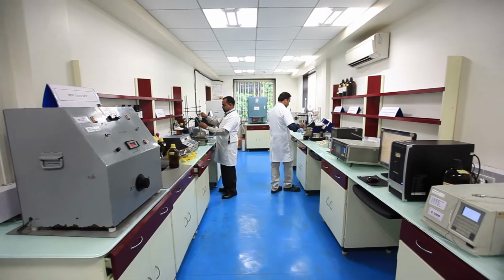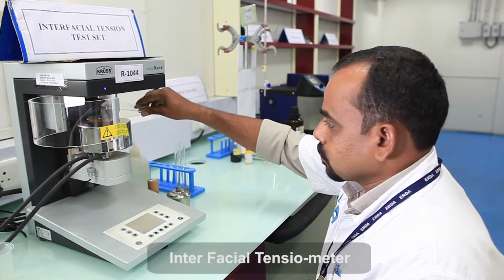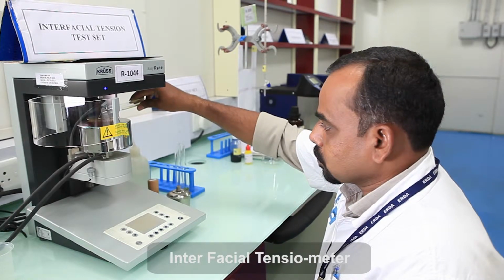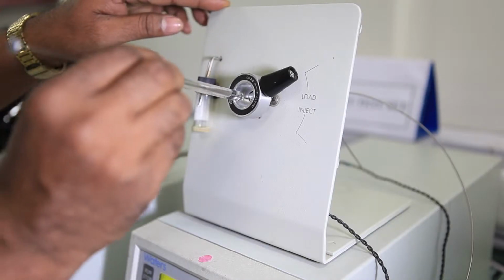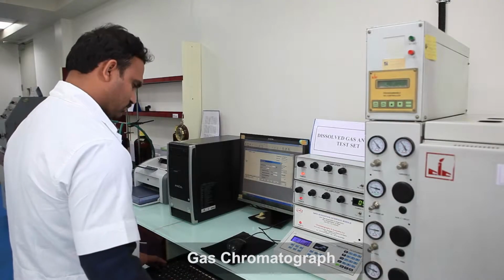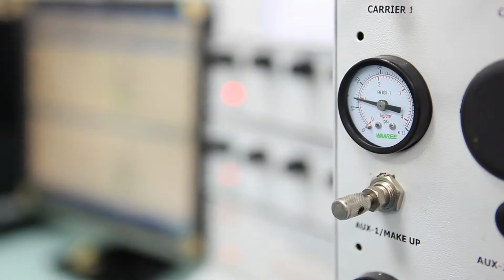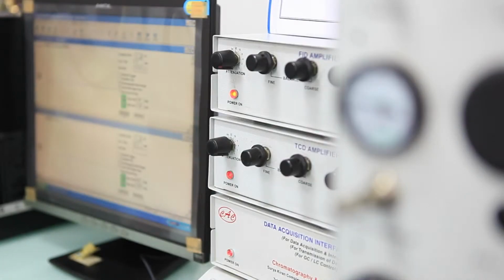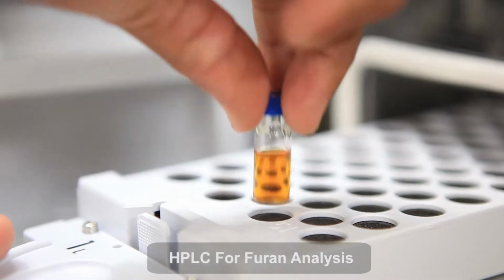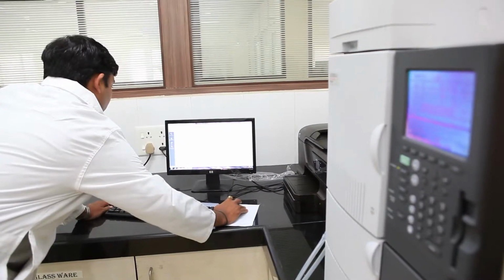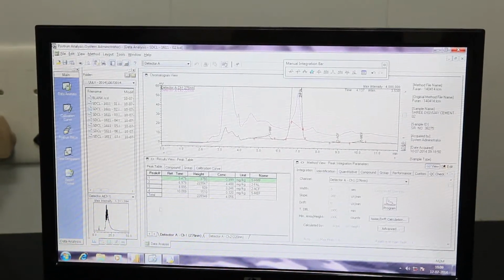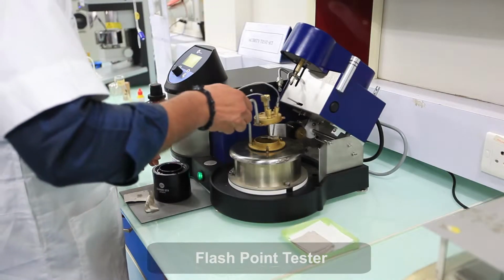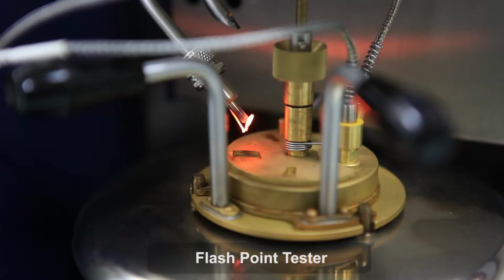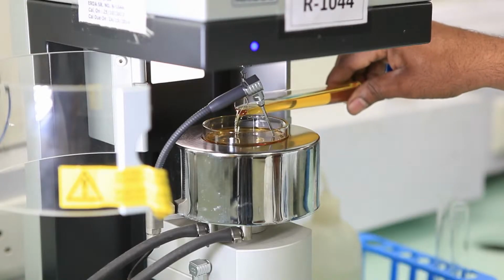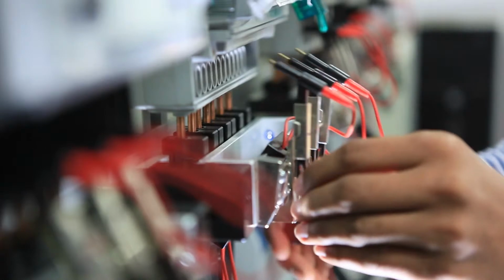We have a modern laboratory for testing of transformer oil as per IS 1866 and have expertise in the interpretation of dissolved gas analysis results as per IS 10593 and Furan analysis results as per IEC 61198. ERDA West is geared up to take up oil testing assignments on annual rate contract basis.